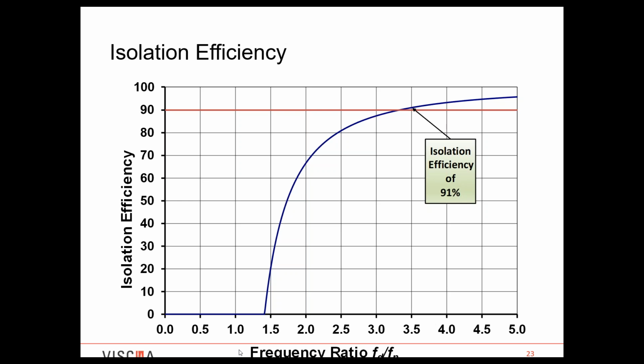And so when you look at your frequency ratio on the horizontal axis here, you're looking at that ratio of the driving frequency to the natural frequency. And to obtain an isolation efficiency curve, which is what we call this blue line, where it crosses the isolation efficiency of 90%, you're looking at almost a frequency ratio of 3.5. So oftentimes you'll hear the rule of thumb that you have to get your driving or disturbing frequency to be almost 3.5 times away from your natural frequency. Now, as we look at this isolation efficiency curve, the blue line, you can see that, yes, ideally you want to approach that 3.5 mark. But at 3, you're well above 85% isolation efficiency. So you have quite a bit of isolation efficiency at that point. And even 2.5 has you at 80% isolation efficiency.